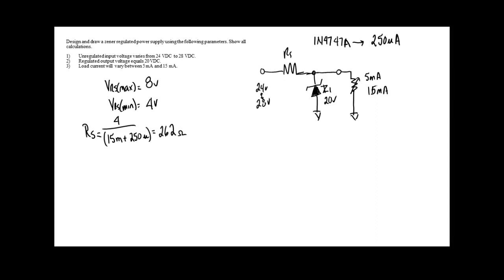Okay, guys, so what size would we use? I'm not going to look it up anymore. Y'all going to look it up. What's that? 240? Okay, so we're going to use 240, and then we're going to check the tolerance. We're going to multiply it by 1.05. That's going to raise it up 5%. What does that get us?